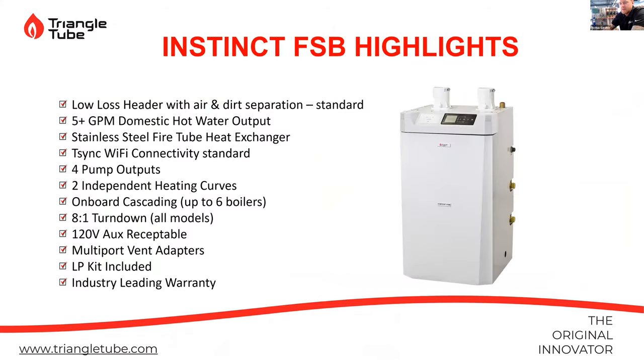And some of the highlights. I went through pretty much all of this. Cascading: our Instinct boilers, all of our boilers pretty much use the same control. On all of our Instincts and Prestiges, we can cascade these boilers up to 6. The only thing you need to purchase is a cascading cable. The cable will plug into the master in the control, and then it goes to the next one, to the next one, to the next one on the board. And you do not need an auxiliary control, a Tekmar, or anything to set these up.